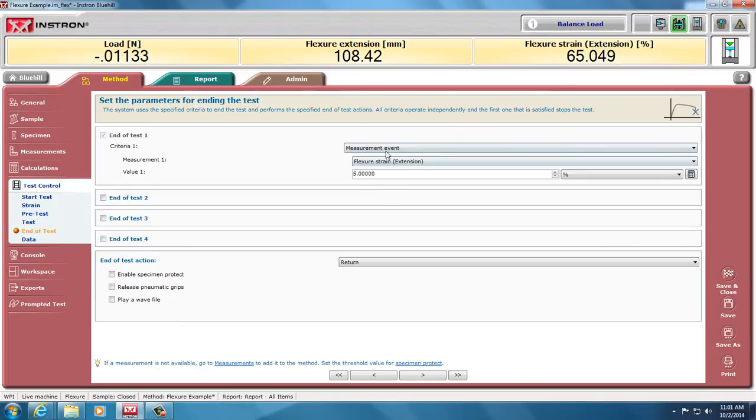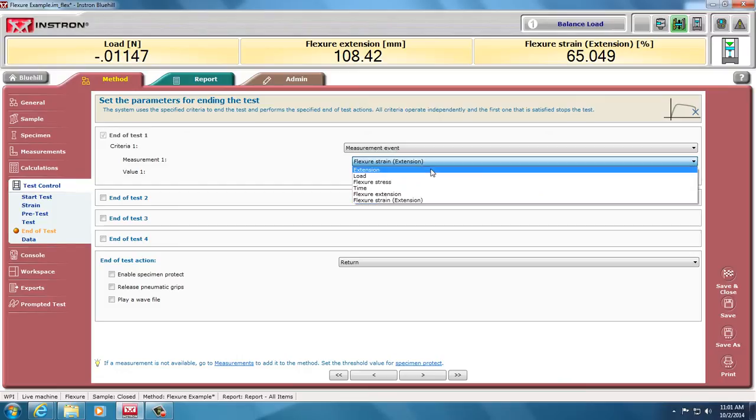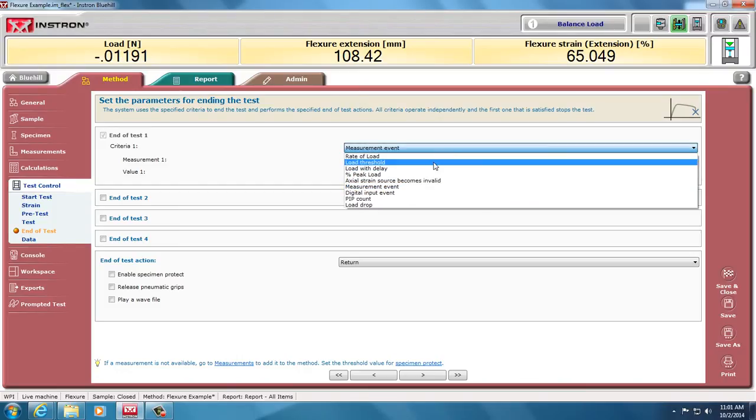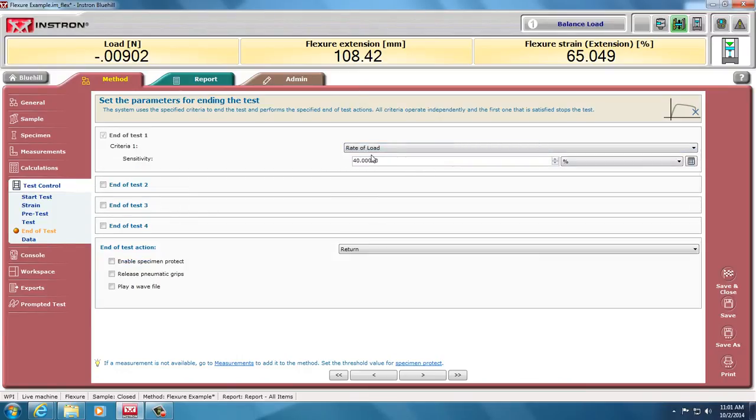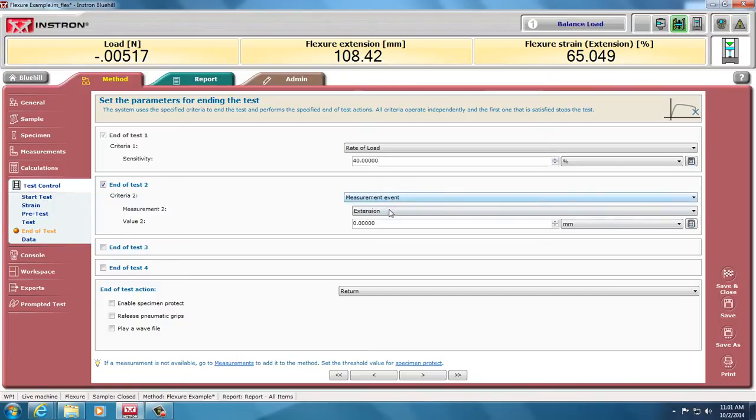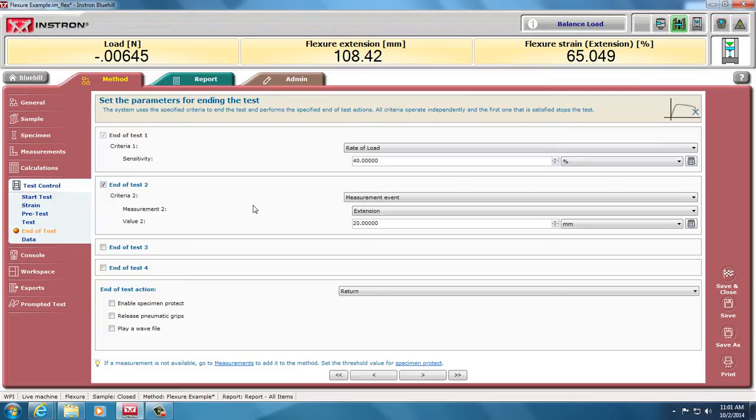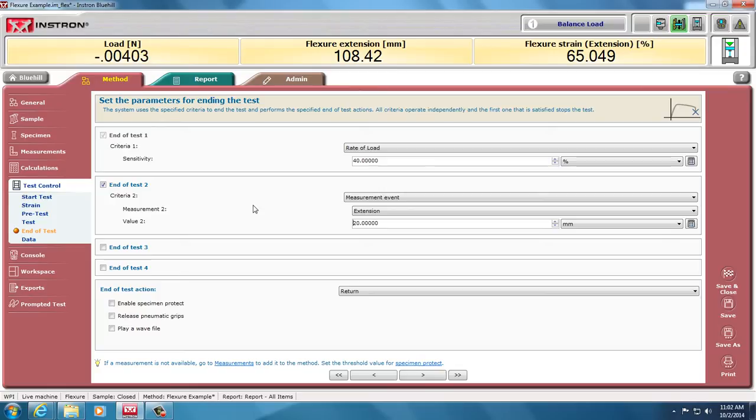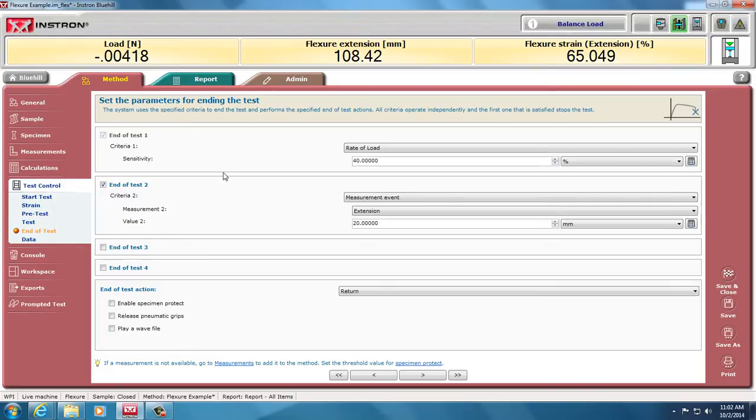But at the end of the test, it could stop at a certain flexural strain. But I want to break my sample, so I'm going to go until the rate of load changes by 40%. And I also don't want to break my machine, so I'll put a stop when my extension is 20 millimeters. Now, when we're doing flexure testing, the machine inverts or puts a negative sign in front of your loads and your displacement. So an extension of 20 millimeters is actually going down in the machine, so a compressive. And the load, positive force, is going to be a compressive load. That makes our stress strain curves and our force displacement curves positive in the upward directions.